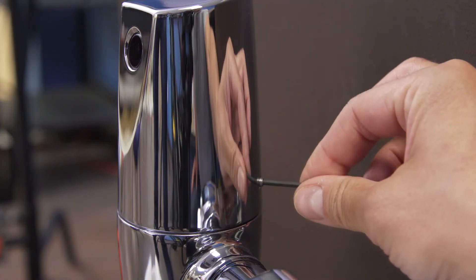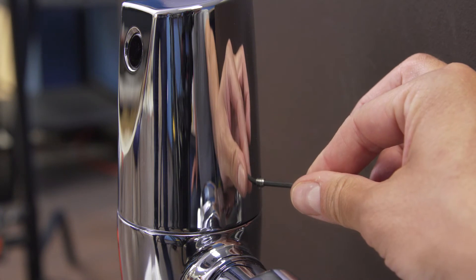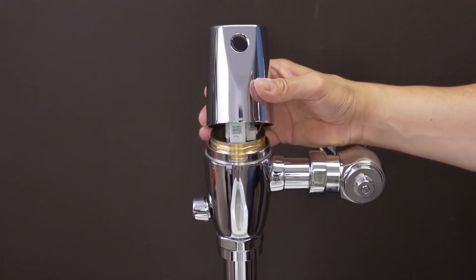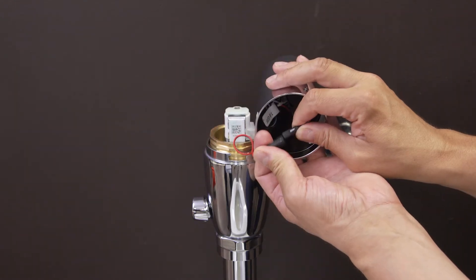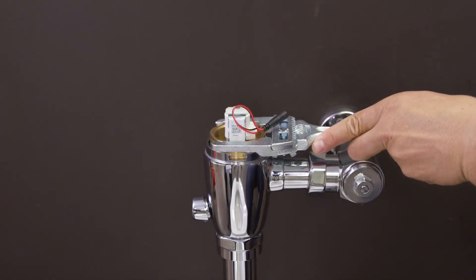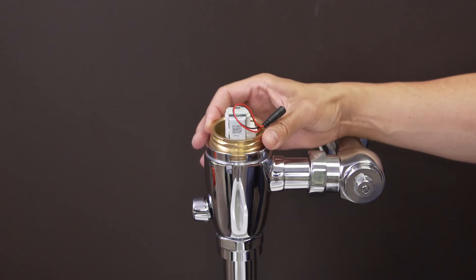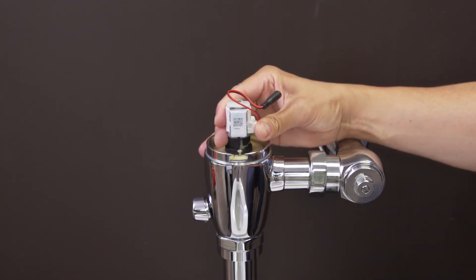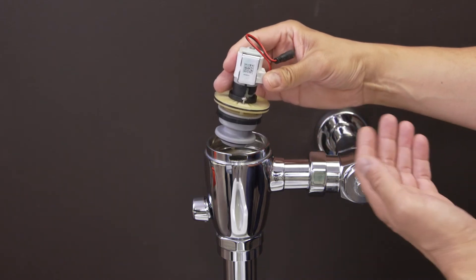Use a 2.5mm hex wrench to loosen the set screw on the back of the cover. Now lift up the cover and unplug the solenoid. Use the smooth jaw wrench to remove the bonnet nut. Gently rock the solenoid back and forth and lift up to remove.